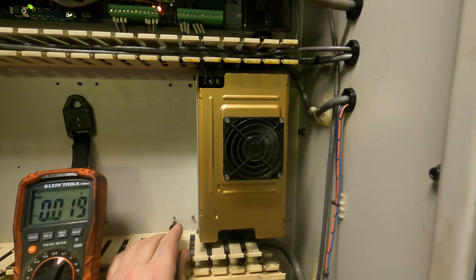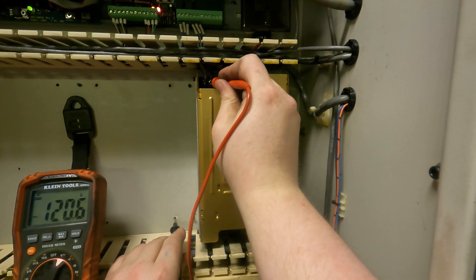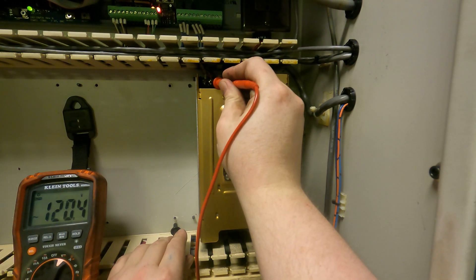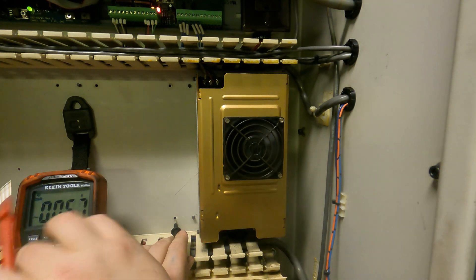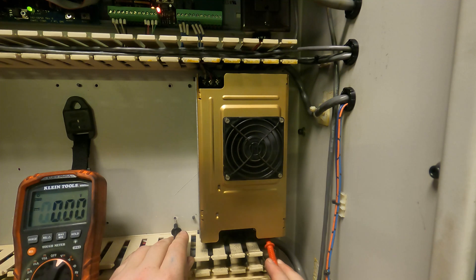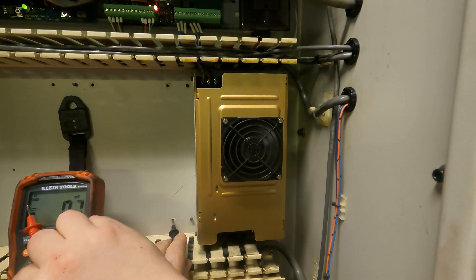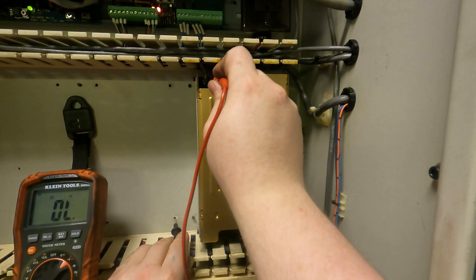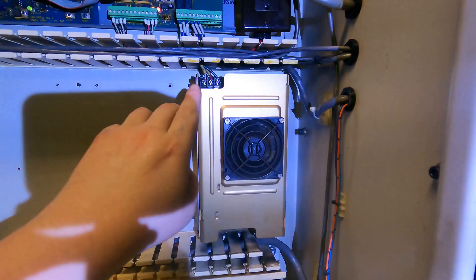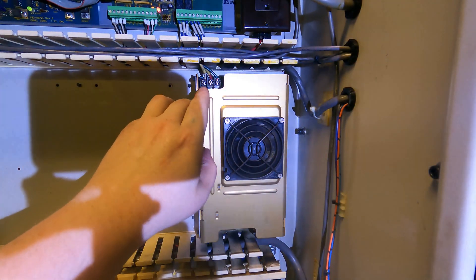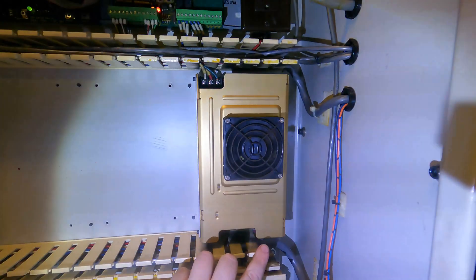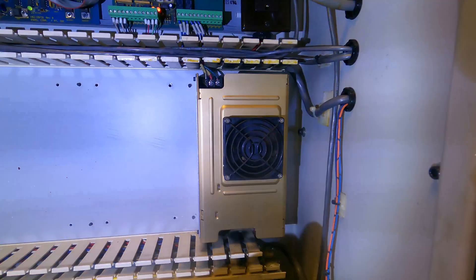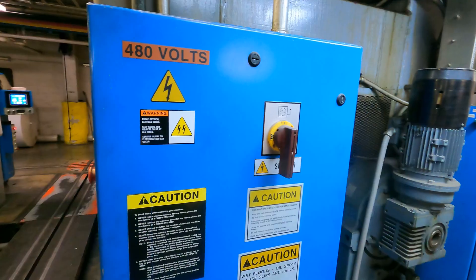We need to know which terminal is positive. So if I connect here just anywhere on the case or a screw or whatever we can see we've got 120 there. So I know the red is positive. And on the bottom the right terminal is positive 24 volts. And then if I go to ohms to the green I can see that that is ground. So I've got neutral positive ground. Red is positive. Neutral is white. Ground is green. And then on the output the positive is on the right. So I just have to make sure that I keep those correct when I'm installing this.